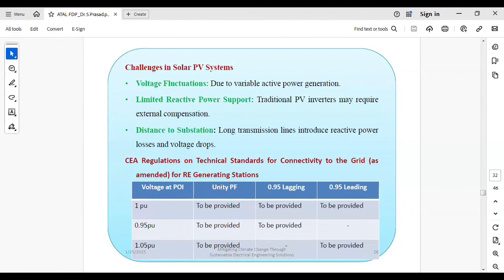So at the point of interconnection, what is the power factor? 0.95. To maintain 0.95 lagging, how much reactive power support is required? To maintain 0.95 leading, how much reactive power support is required? For various voltage levels at the grid. That means when the grid voltage at the point of interconnection is maintained at 1 per unit, then to have 0.95 lagging, what should be the size of the capacitor bank? What should be the size of the reactive power compensating device? That you need to analyze by performing this test.